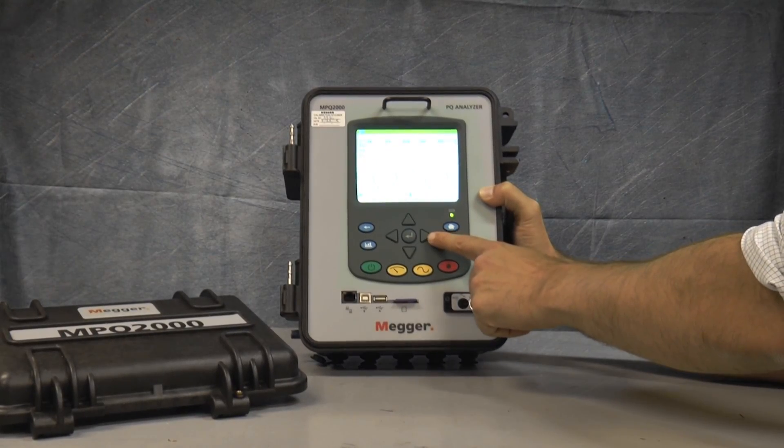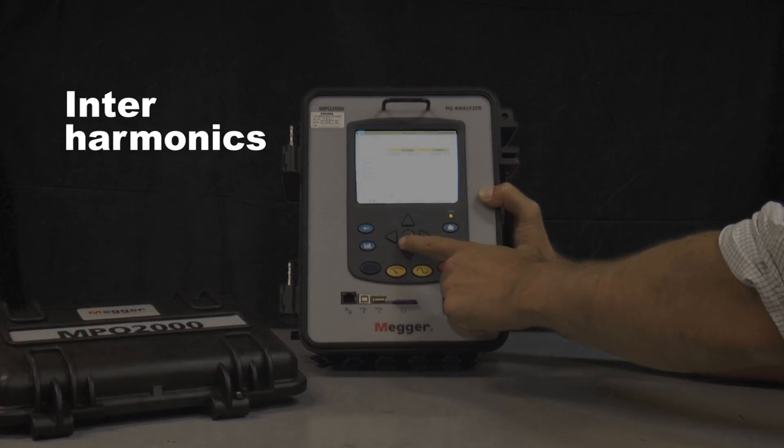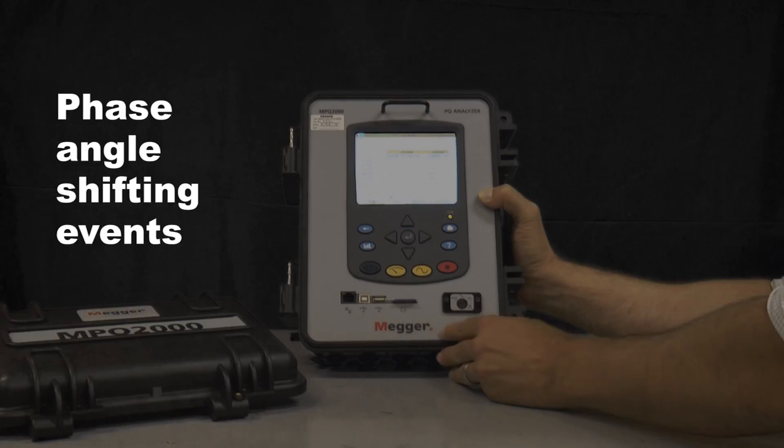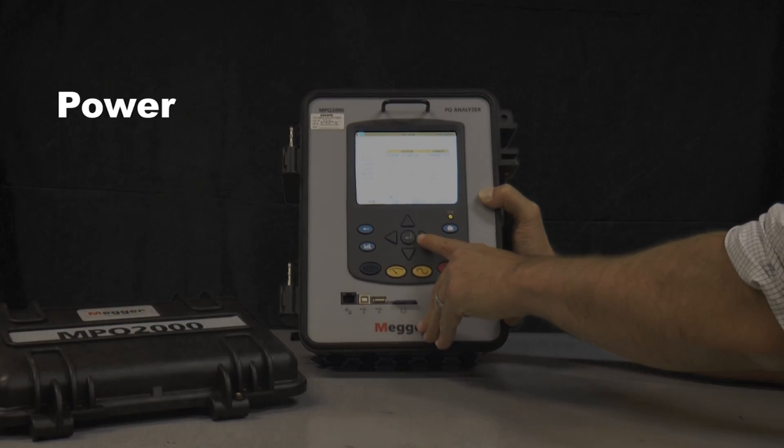Recording parameters such as RMS, dips, swells, transients as fast as one microsecond, as well as harmonics, interharmonics, RVC, mains signaling, phase angle shifting events, power, energy, and much more.